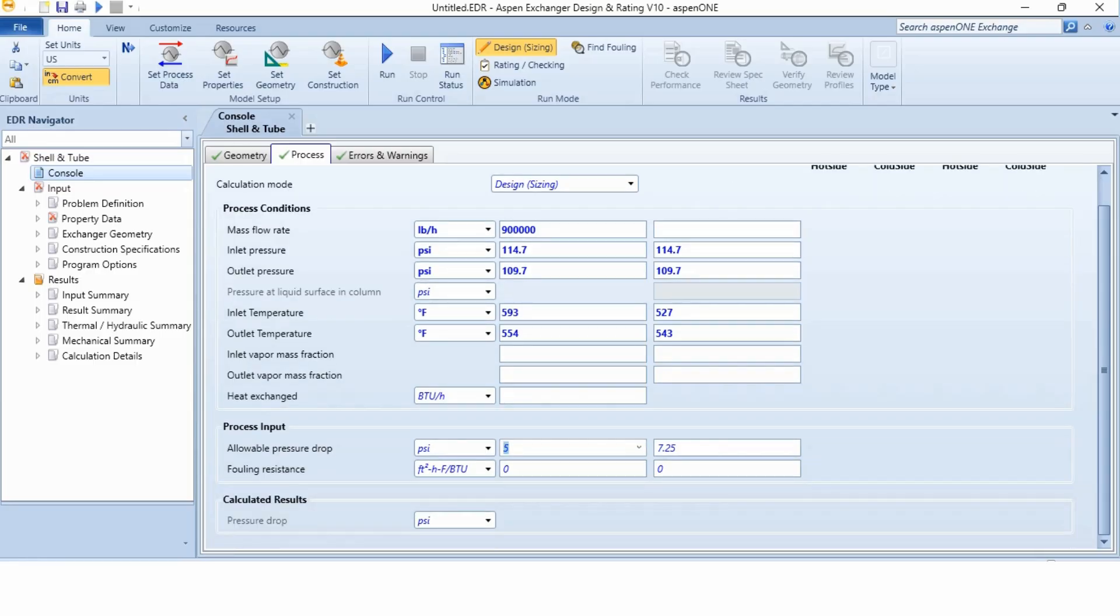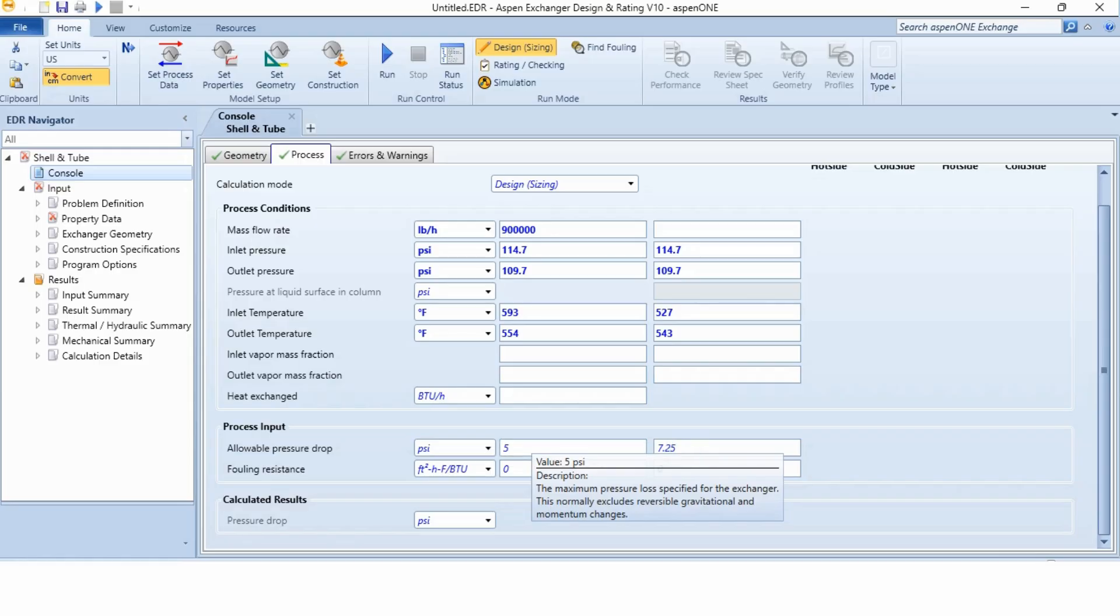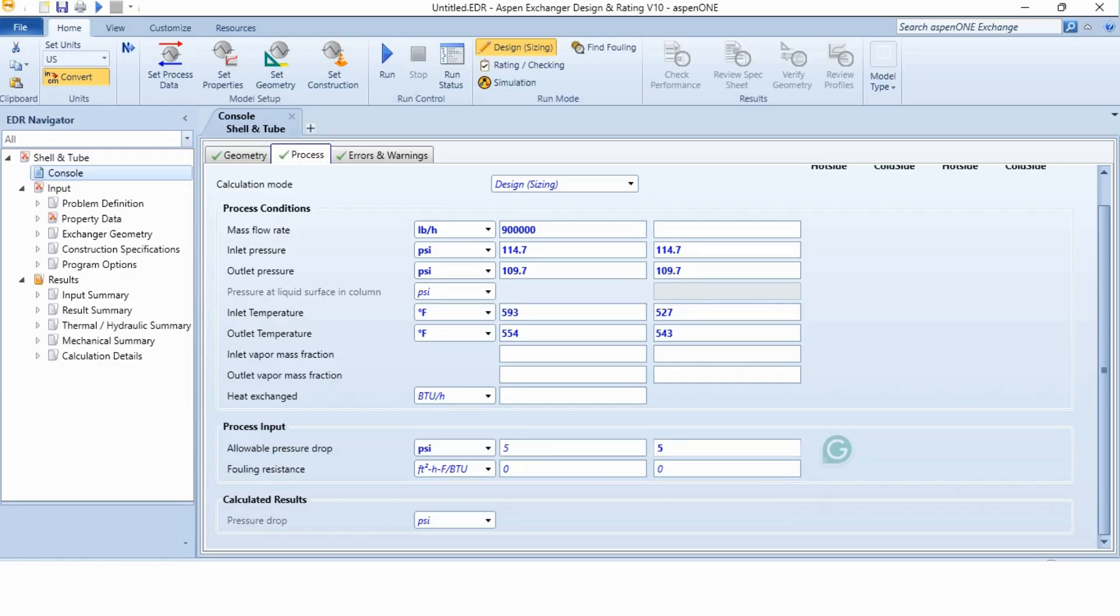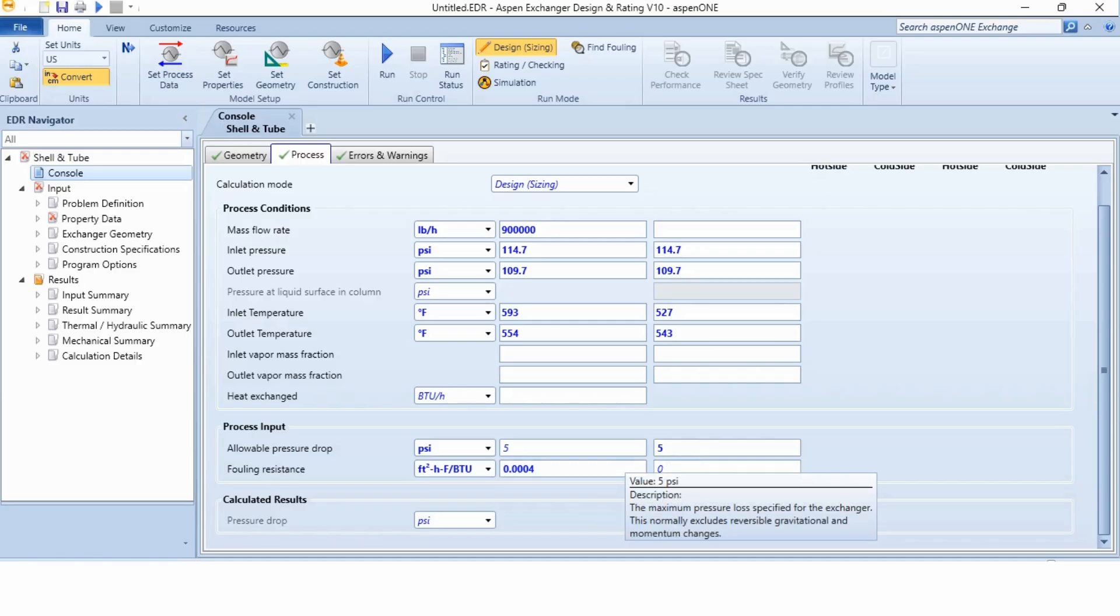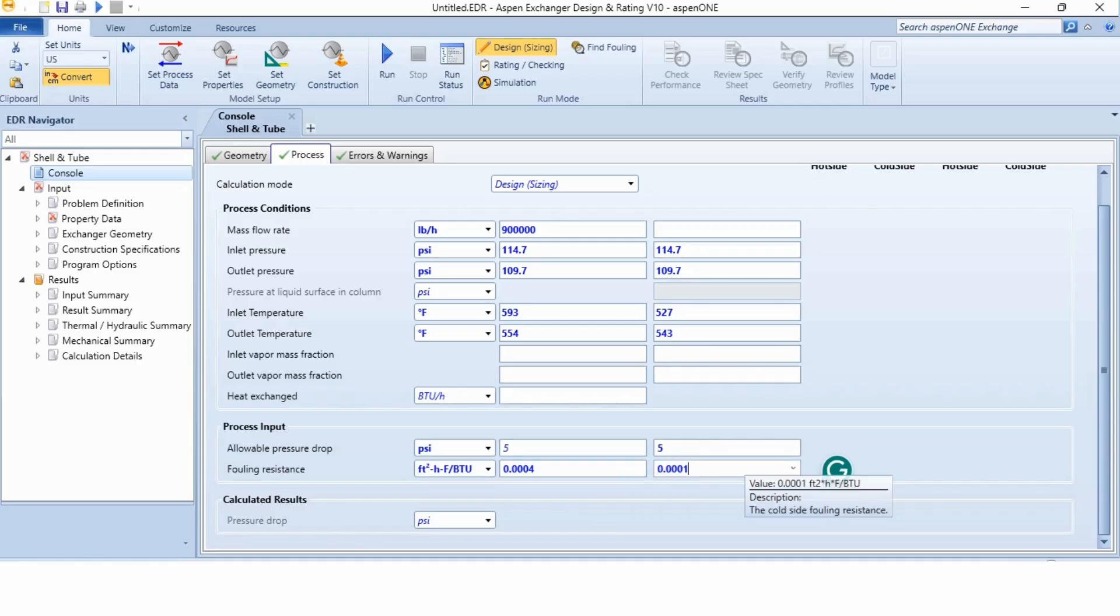Now you can see that all the sky blue boxes have been vanished because we have given the required specification to this system. In allowable pressure drop, this side for hot side and for cold side, it is 5 psi. While the fouling resistance is 0.0004 for hot side and 0.0001 for cold side. And you can see the process is ticked now. We have given all the required specifications in this box.